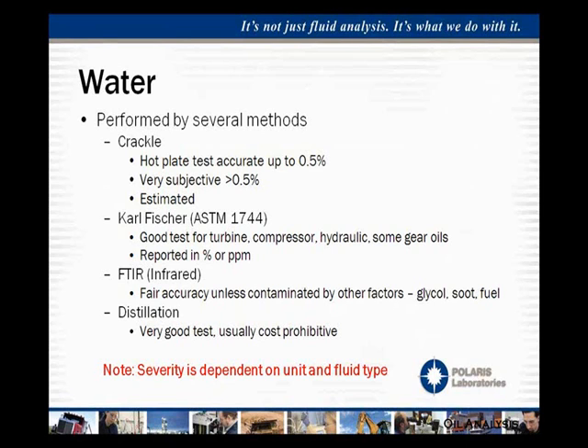When you need exact amounts, that's when we use the Karl Fischer method, using ASTM method 1744 for this calculation. This is what you would want to use for turbines, compressors, hydraulics, and some gear oils depending on the specific application. It's reported in percent or parts per million depending on the lab or how you want to see the results. It's a very exact test used for applications where you need a very low amount of water and need an exact count. Other methods include FTIR — Fourier Transform Infrared Technology — which is fairly accurate unless there's other contamination like glycol or soot, but can be slightly expensive. Distillation is another good method but is usually cost prohibitive for regular use.